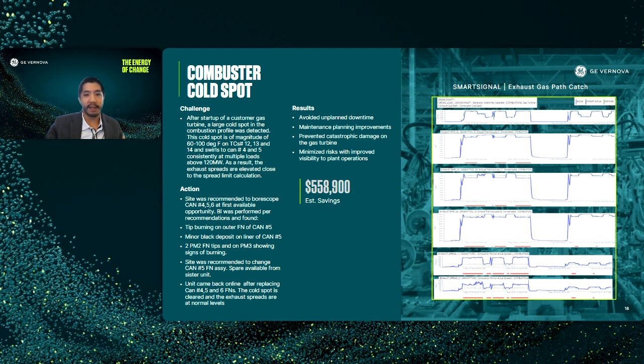SmartSignal recognized the correlated deviations across these multiple thermocouple locations. It flagged it, giving the team time to plan a borescope inspection rather than respond to an emergency. During that borescoping, they found tip burning on the fuel nozzle and minor black deposits on the liner. By replacing the nozzle assembly early, they avoided major damage and an unplanned shutdown.